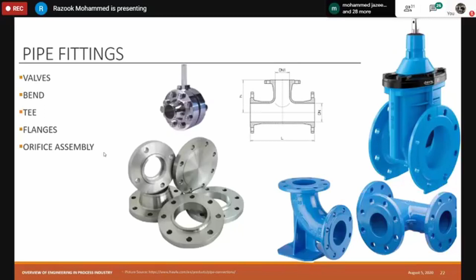Finding discharge rate is correct. And there is one more measurement, flow rate. Correct, very good. So it is good for measuring flow rates. You measure the upstream and downstream pressure, and that gives an indication of the flow rate measurement. It is also used for restricting the flow. Increase flow velocity is also correct. The intention normally is to reduce the pressure and reduce the flow, but the effect of the orifice will increase the velocity, that is true. It is also called a restriction orifice or measurement orifice.